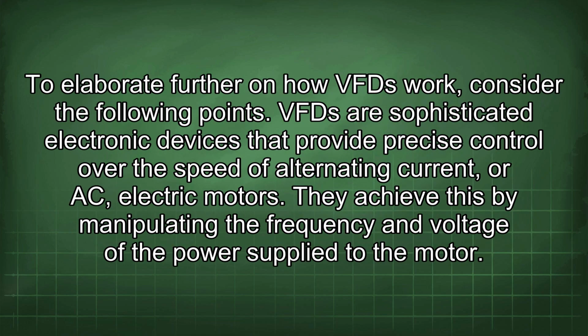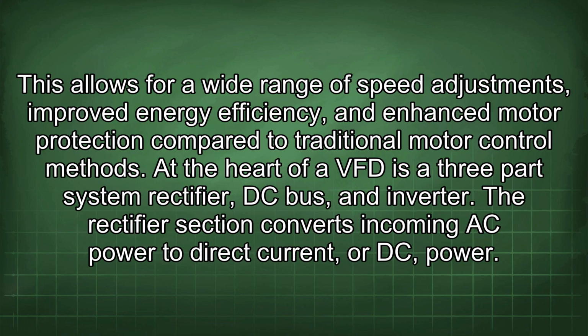To elaborate further on how VFDs work, consider the following points. VFDs are sophisticated electronic devices that provide precise control over the speed of alternating current, or AC, electric motors. They achieve this by manipulating the frequency and voltage of the power supplied to the motor. This allows for a wide range of speed adjustments, improved energy efficiency, and enhanced motor protection compared to traditional motor control methods. At the heart of a VFD is a three-part system: rectifier, DC bus, and inverter.